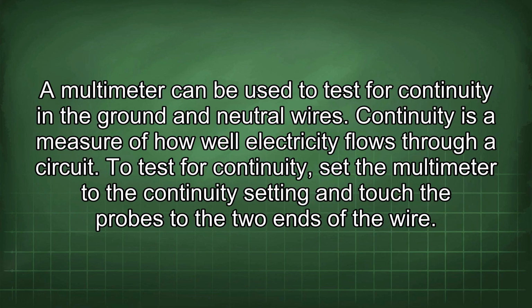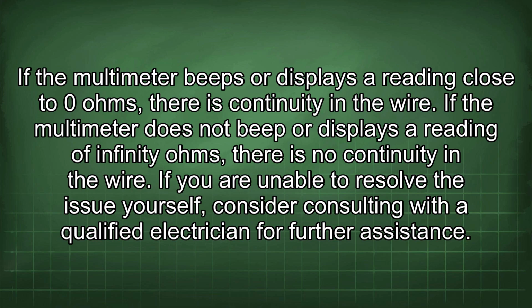A multimeter can be used to test for continuity in the ground and neutral wires. Continuity is a measure of how well electricity flows through a circuit. To test for continuity, set the multimeter to the continuity setting and touch the probes to the two ends of the wire. If the multimeter beeps or displays a reading close to 0 ohms, there is continuity in the wire. If the multimeter does not beep or displays a reading of infinity ohms, there is no continuity in the wire. If you are unable to resolve the issue yourself, consider consulting with a qualified electrician for further assistance.